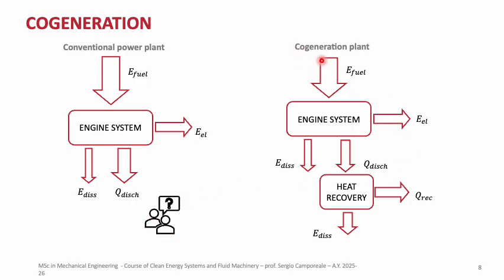On the right, in a cogeneration plant, the same electric energy is produced, but the discharged heat is recovered. It is sent to a heat recovery system here, and part is recovered and can be used for industrial purposes, as district heating, for example, or industrial applications. As a result, cogeneration improves the fuel utilization and increases the overall efficiency.